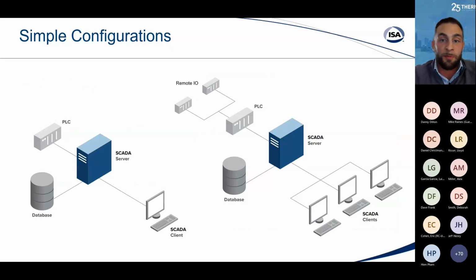I want to look at some sample configurations of a PLC SCADA system to give you a better idea of how the pieces play together. The first one, on the left, is a bare-bones, minimum, very simple system. At the top we have a PLC—we can assume there's an I/O interface in the chassis—and that's communicating and pulling data from devices on the plant floor, sending commands to valves and pumps. The SCADA server is connected to the PLC, pulling data in real time from that PLC and the devices on the plant floor.